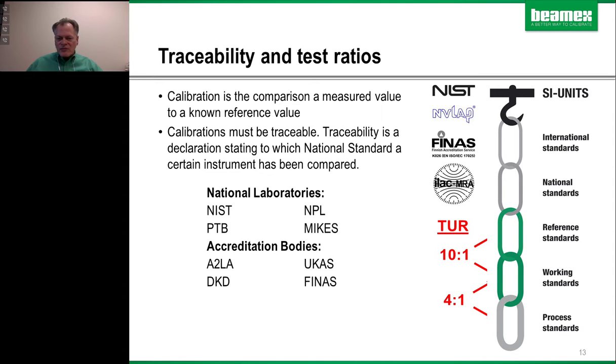And then here's this pedigree that I was talking about. So when you make a calibration on a process instrument, you're using a calibrator that's certified. That calibrator was certified by a reference standard, and then those go back to national standards and ultimately international standards. And one of the good rules out there, it's kind of an old military standard, is you want to have a 4-to-1 ratio. In other words, your calibrator should be 4 times as accurate as what you're trying to achieve in the process. So for those of you that are working under 0.5%, that means your calibrator needs to be like 0.1%, or even if you're down at 0.25%, it needs to be something like 0.05% of span or reading, whatever the ratio is, to get that good traceability.